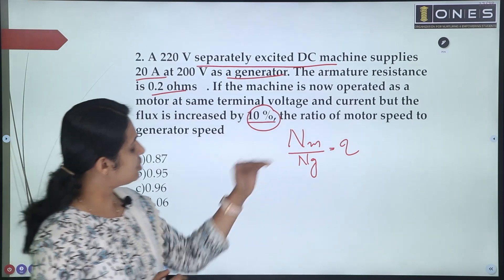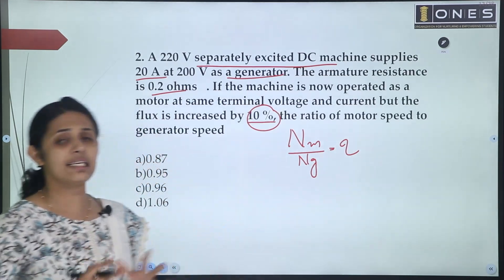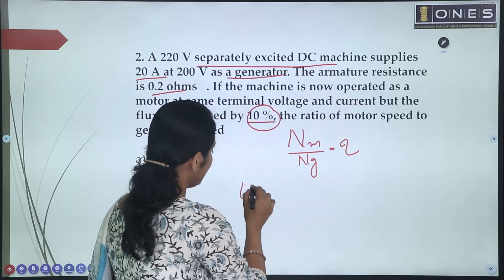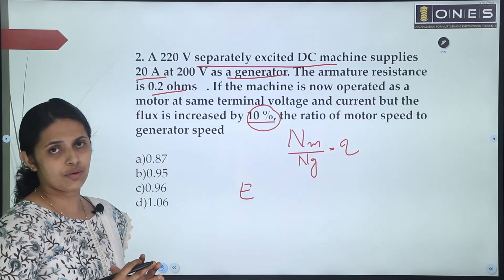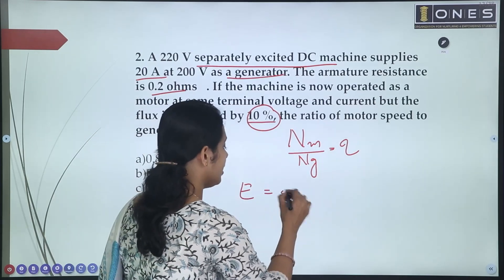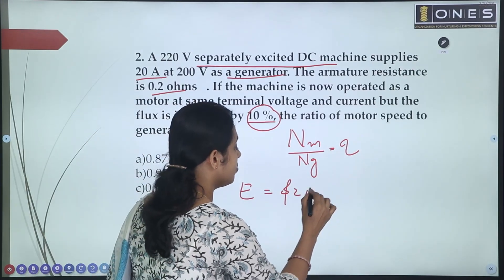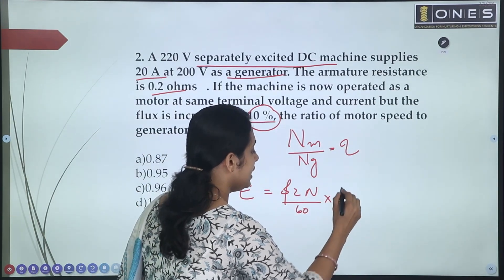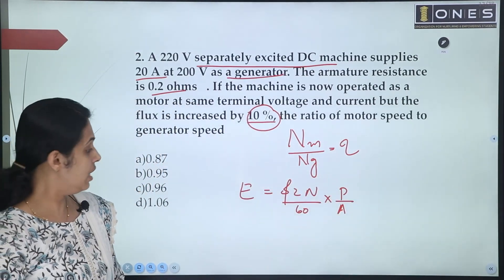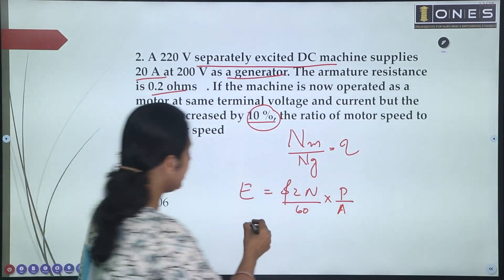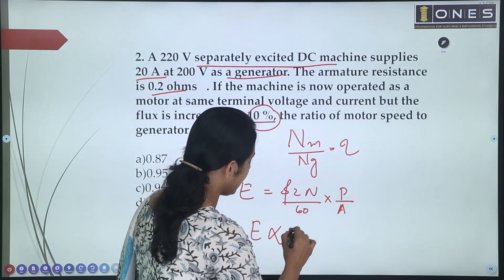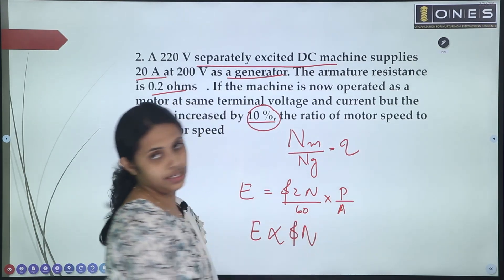We need to calculate Nm by Ng. The general equation for generated voltage is E = (ΦZN/60) × (P/A). So generated voltage E is directly proportional to Φ × N, since P and A are constant.